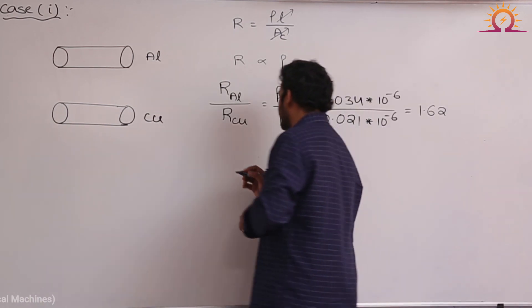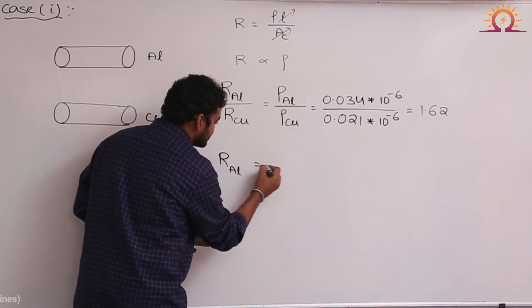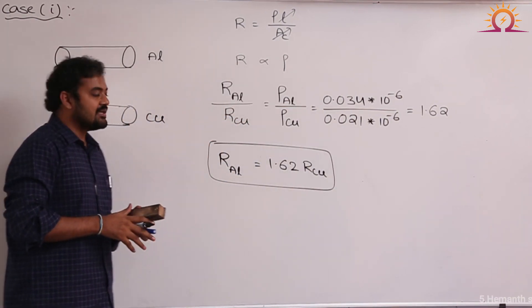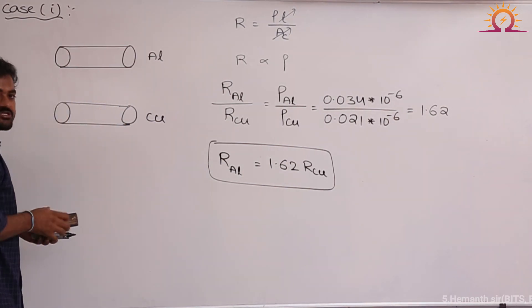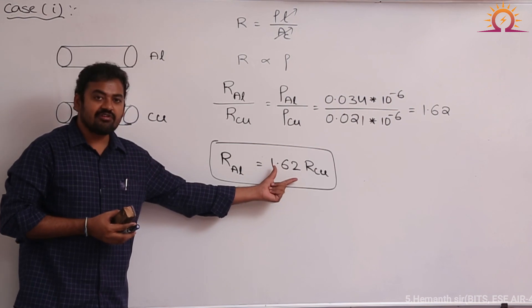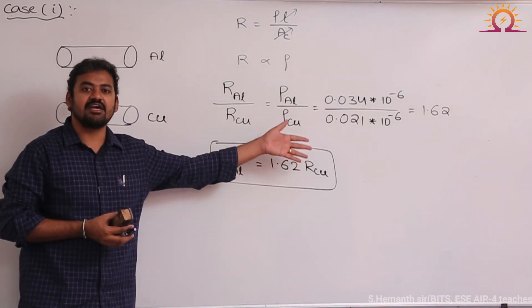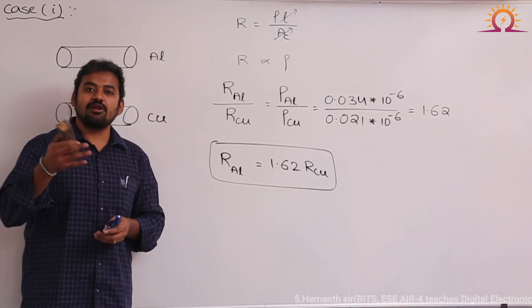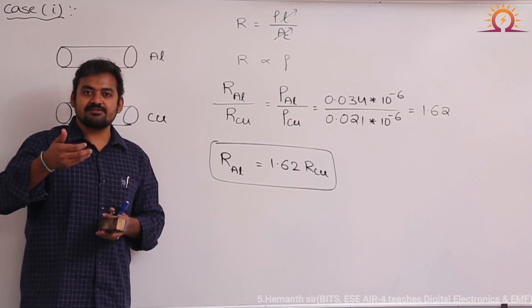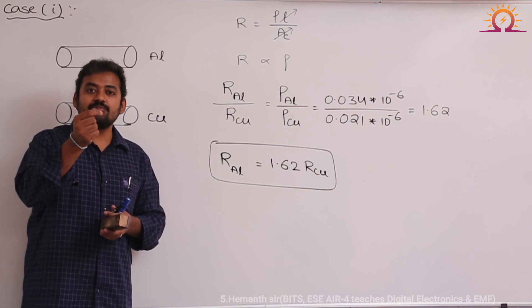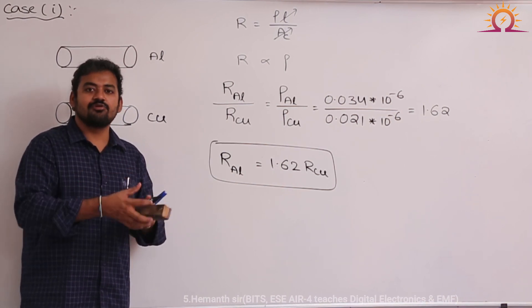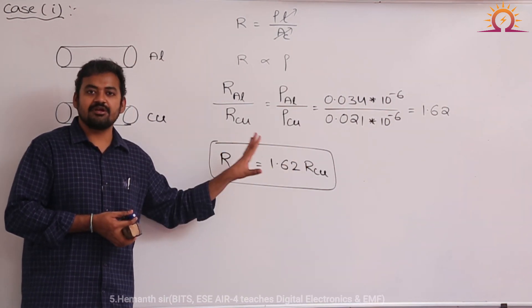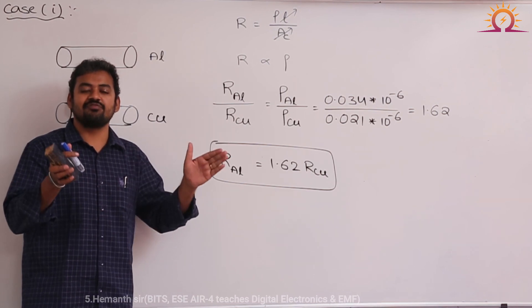Comparing at an average temperature of 75 degrees centigrade — which is the typical full load condition inside a machine — aluminum resistivity is 0.034 × 10⁻⁶ and copper resistivity is 0.021 × 10⁻⁶. This ratio works out to approximately 1.62. Therefore, aluminum conductor resistance is 1.62 times copper conductor resistance. For a given size (same length and cross-sectional area), aluminum winding will offer 62% more resistance than copper. If resistance is more, copper losses will be more; if copper losses are more, temperature will rise more; if temperature rises more, the melting point will be reached very quickly. Therefore, aluminum usage in electrical machines is limited, and copper is the most superior material.